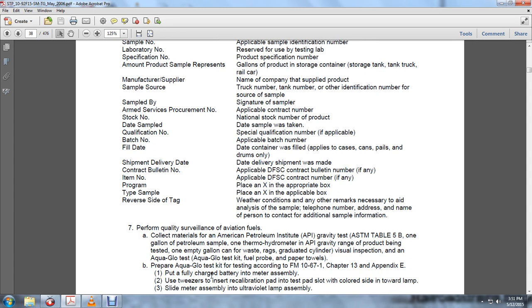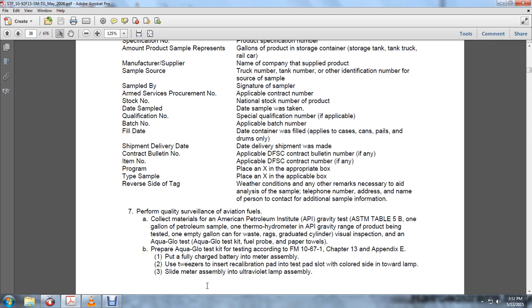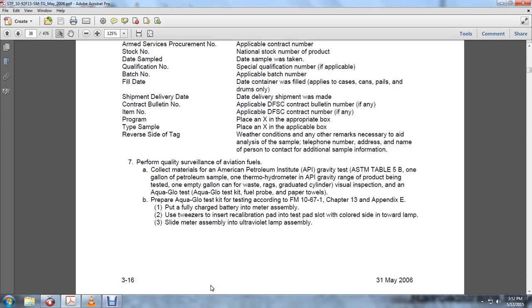Rags, graduated cylinder, visual inspection and an Aqua-Glo test of the fuel, a probe, and paper towels. Prepare the Aqua-Glo test according to Field Manual 10-67-1, Chapter 13, Appendix E. Put the fully charged battery into the meter assembly. Use the tweezers and insert the calibration pad into the test pad slot, color side down toward the lamp. Slide the meter assembly into the ultraviolet lamp assembly.